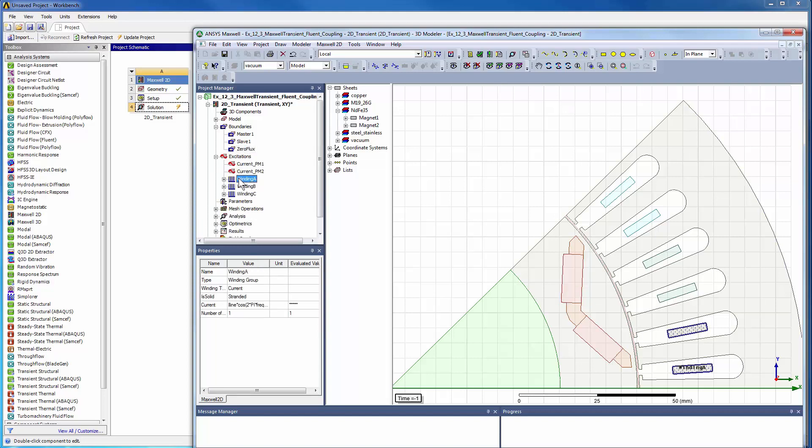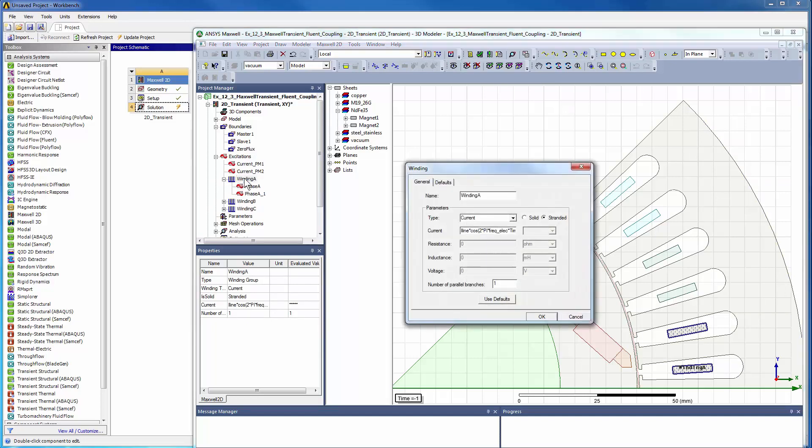Maxwell handles the winding topology where the coils are grouped based on a three-phase imposed current, voltage, or external circuit excitation. Here we assign a current source to avoid electromagnetic transients to get a faster steady-state transient solution to generate losses for the computational fluid dynamics.